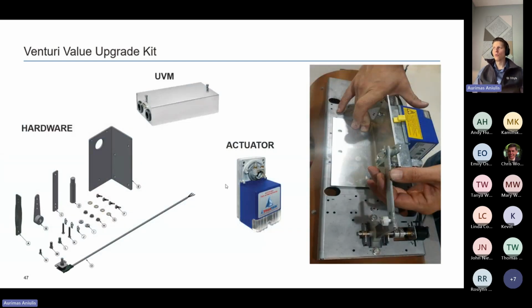And the kit is fairly simple. What you're seeing here is a Phoenix air valve where we remove their controls and their actuator, and we add our linkage, our position sensor, and our actuator with the UVM. Then we look at their label and their flows to voltage, and we either enter those into the UVM manually or we do an in-field calibration to populate that lookup table that we discussed before. And what this allows you to do is now have digital control, 0-10 in, 0-10 out, and that space can now be brought into your building automation umbrella.